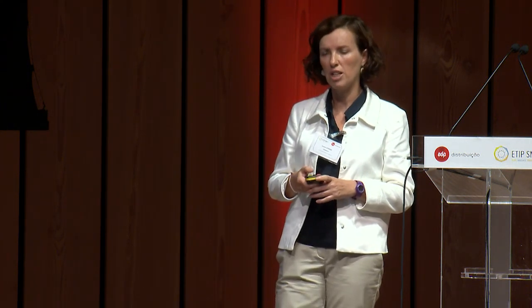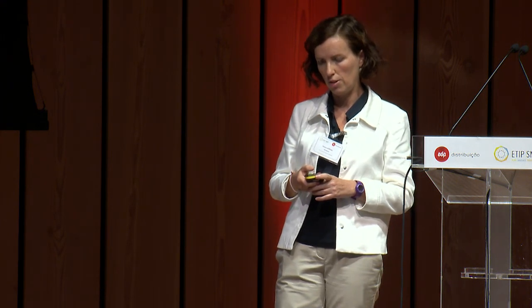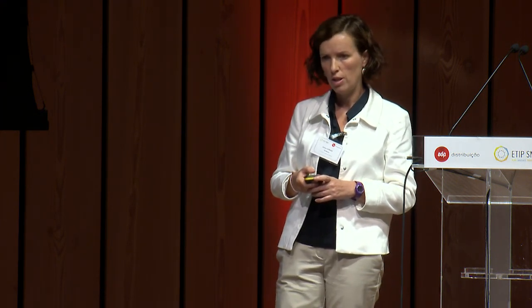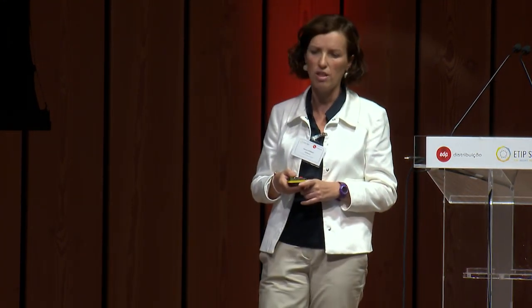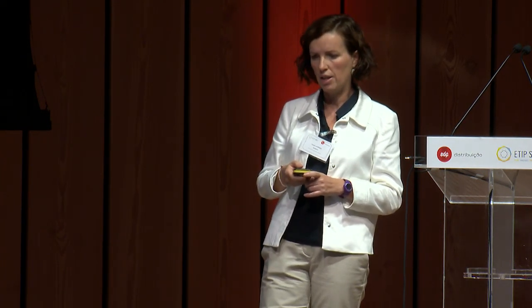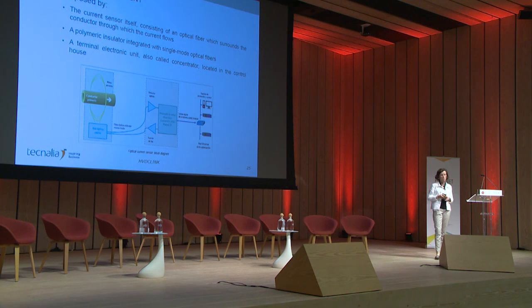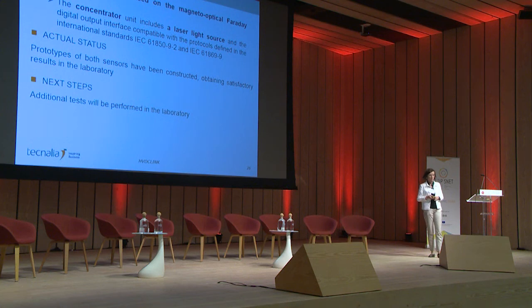For the current measurement, this is an optical solution. This is a diagram of this solution. It is composed of the current sensor itself, an insulator, and a terminal electronic unit, also called a concentrator. The operating principle is based on the magneto-optical Faraday effect, and the concentrator includes an optical part, a laser light source, and also a digital output interface, compatible with typical standards.